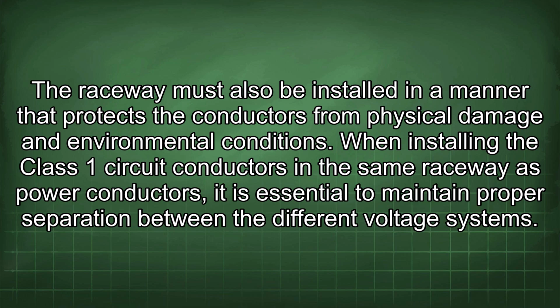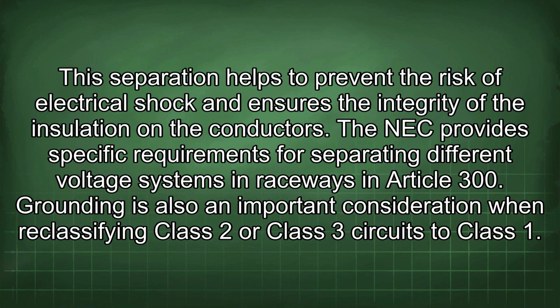When installing the Class 1 circuit conductors in the same raceway as power conductors, it is essential to maintain proper separation between the different voltage systems. This separation helps to prevent the risk of electrical shock and ensures the integrity of the insulation on the conductors. The NEC provides specific requirements for separating different voltage systems in raceways in Article 300.